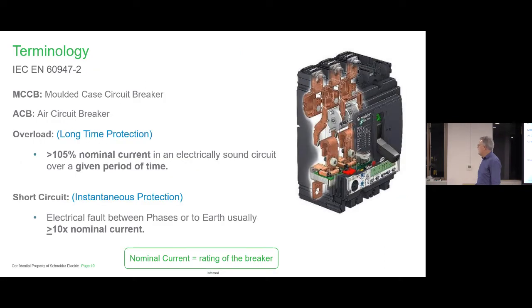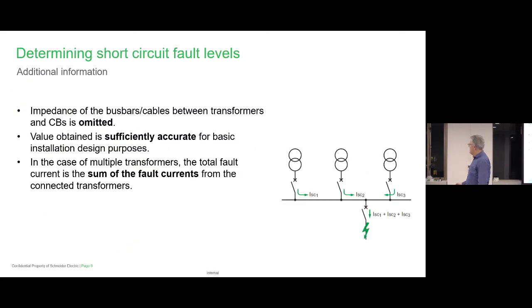And then when we're calculating the fault level and the devices around this area here, we have to also consider that you might have a bus coupler in here and you might have a generator. So we need to do the settings, and the protection calculations around a variety of different setups. We need to take that into account.